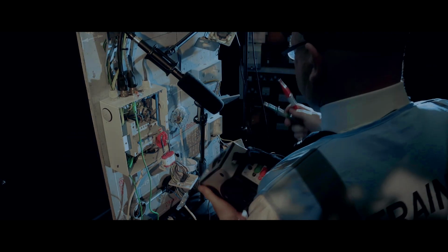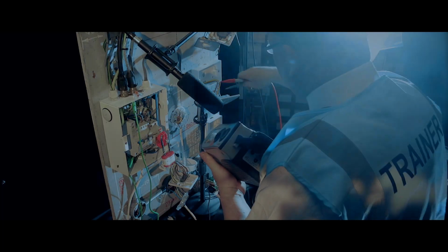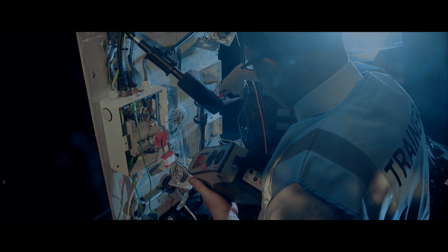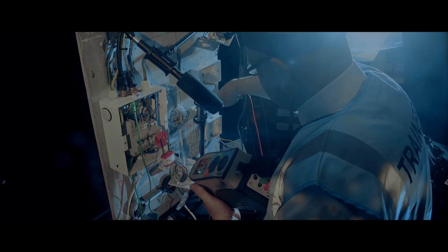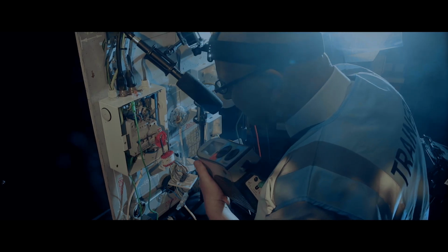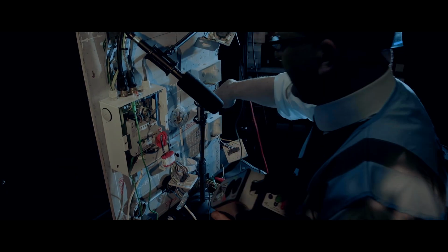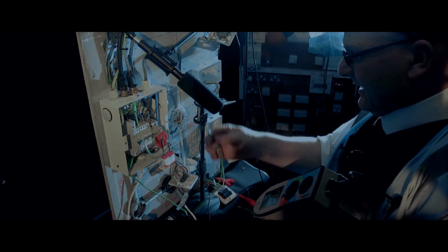So let's now have a look at what we can do from the back of the end of line of our socket circuit between line and CPC in that socket, and it's 0.06, 0.05. And that's because we've got this link lead in.